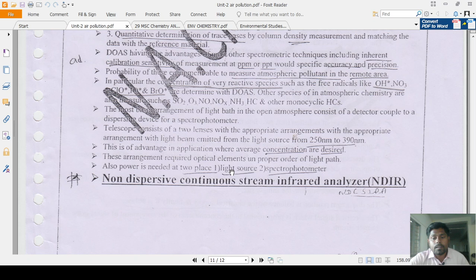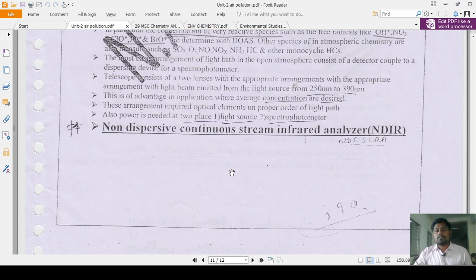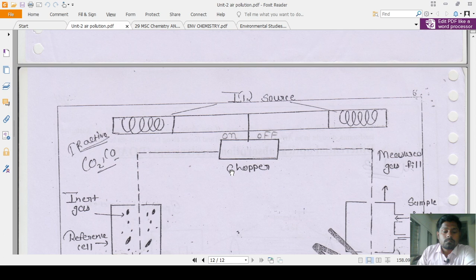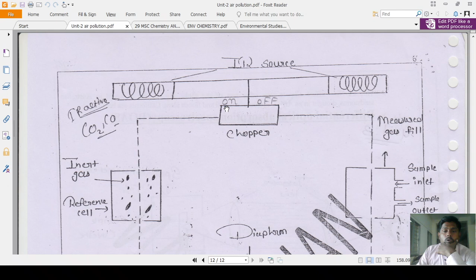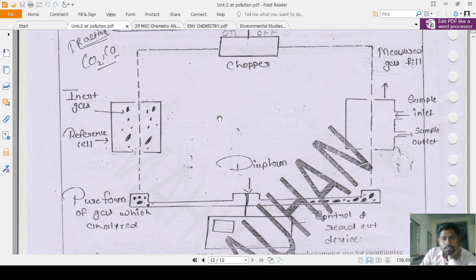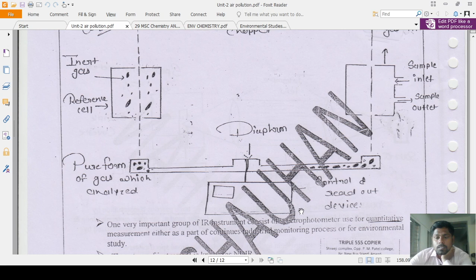Now, the non-dispersive continuous stream infrared analyzer, NDIR. That is the diagram. The IR source is here, that is the chopper, the on-off condition is here, and the IR active materials like CO2, CO, the measured gas, fill here. The sample inlet, the sample outlet is here, and that is the inert gas, and the reference cell is also here, with the pure form of the gas which is analyzed. That is the reference, that is the diaphragm, that is the controller, and the readout device is here.